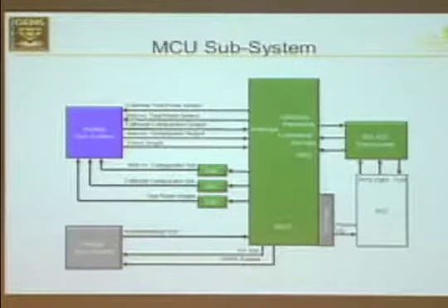We've got 3 DACs that are used for setting the test pulse height for that pulsing circuitry, as well as 2 of them for the different comparators for our noise discrimination on those event lines. We also have the housekeeping from the voltage system, some control lines, and another passive thermistor inside our electronics box so we can tell the temperature there.